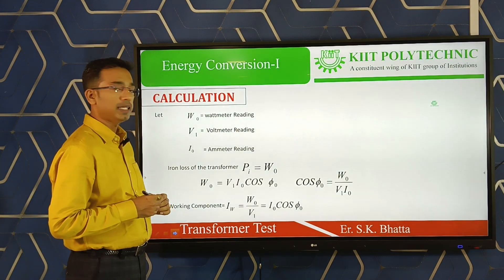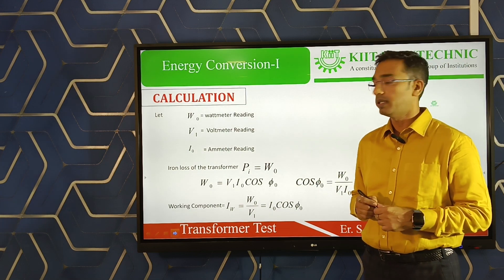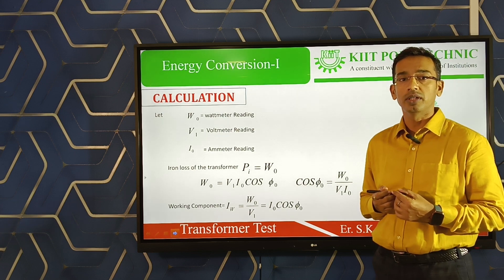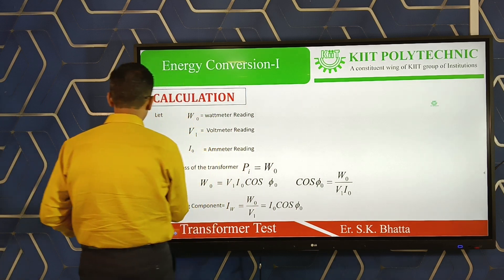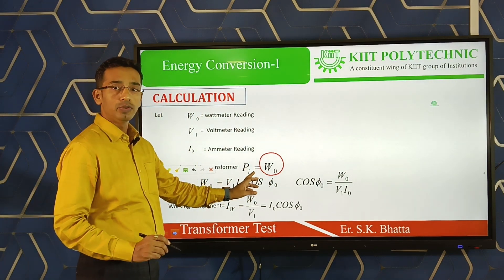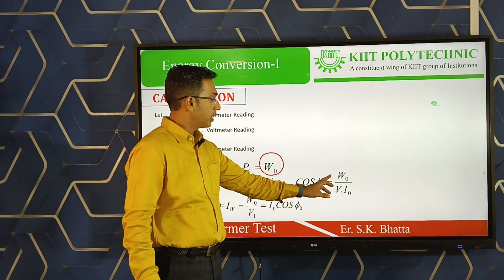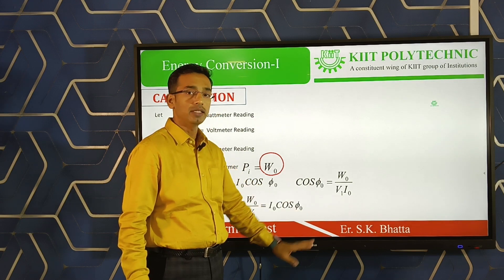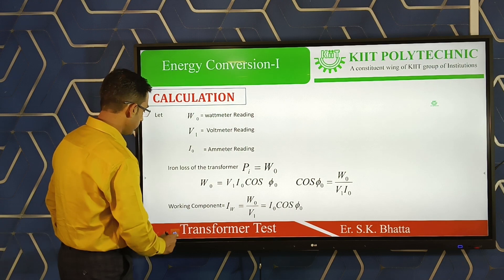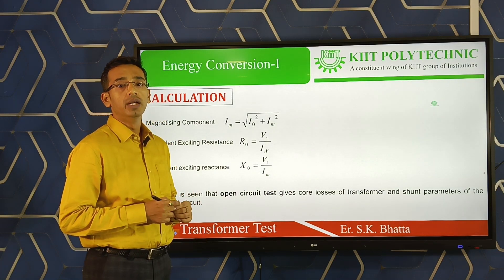For the calculations: W₀ is the wattmeter reading, I₀ is the ammeter reading (no-load current), and V₁ is the voltmeter reading. The wattmeter reading gives the iron loss: Pᵢ = W₀. The no-load power factor is cos φ₀ = W₀ / (V₁ × I₀). The working component of current is Iw = I₀ × cos φ₀.